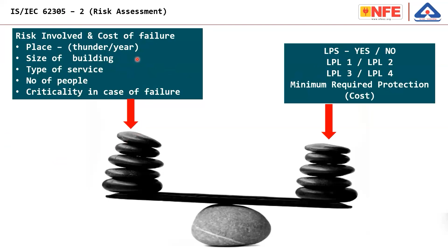The idea is 1 out of 10 to the power 5, that means about 1 lakh strikes, must be protected for humans. For example, out of 1 lakh lightning strikes, only 1 lightning strike shall be harmful to a person. Similarly, for electronics, 10 to the power of 3, that means out of 1,000 strikes, 1 lightning strike can be harmful to electronics. So these are the tolerable risks. Always, the risk assessment is to ensure that by installing lightning protection, the risk is reduced to less than the tolerable limit.